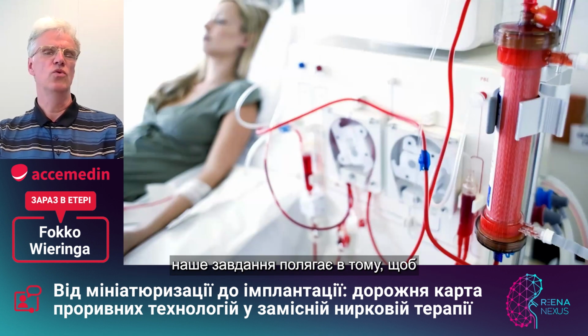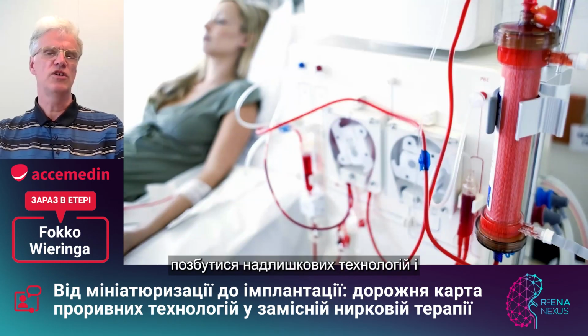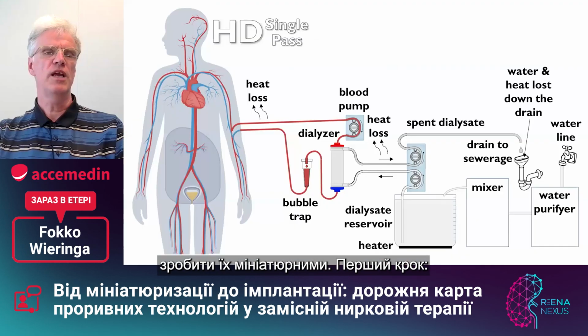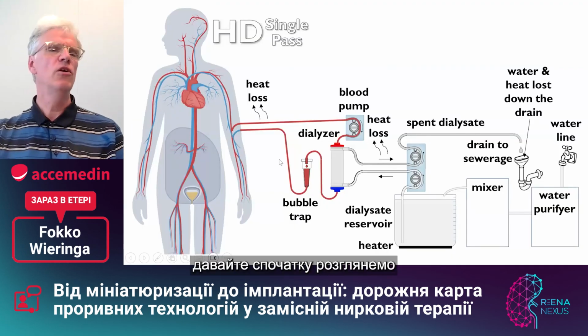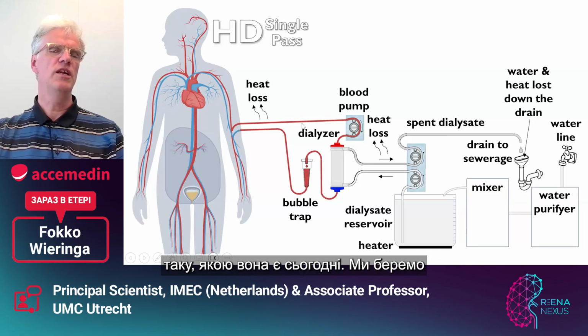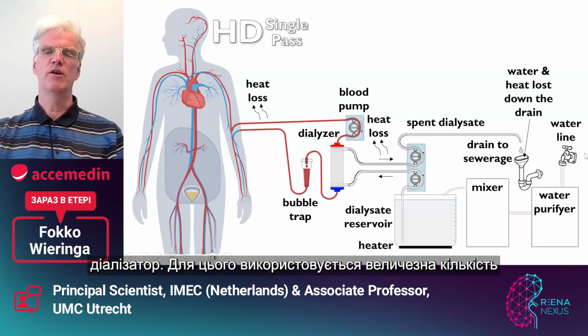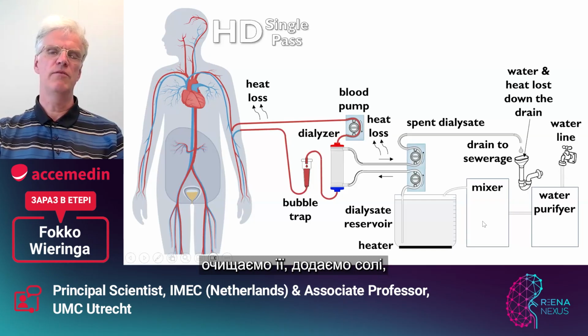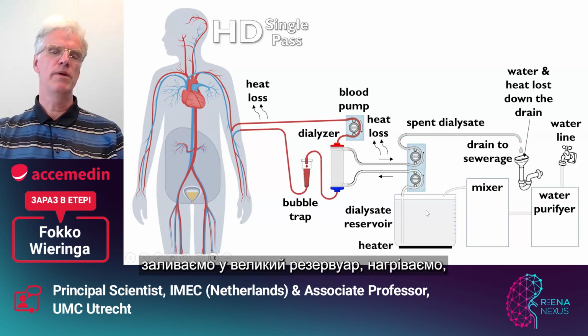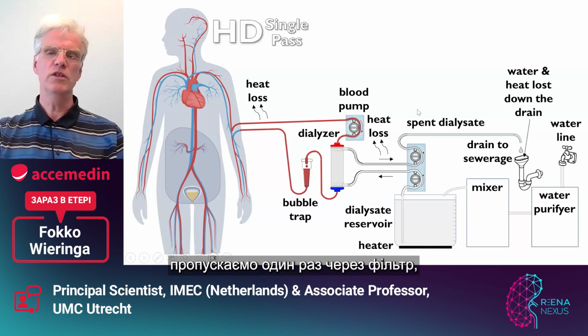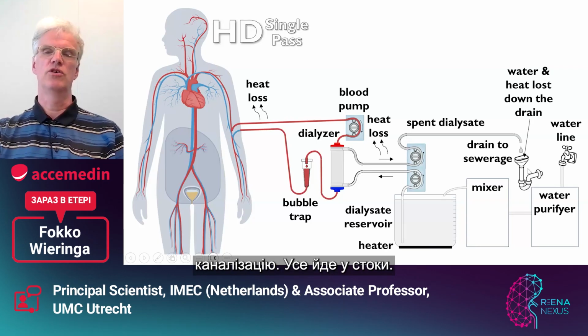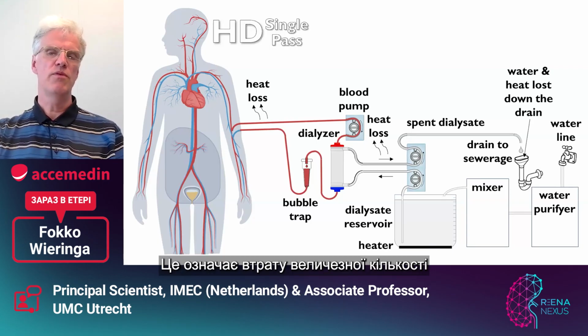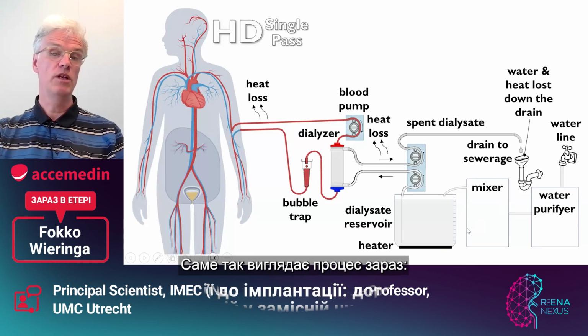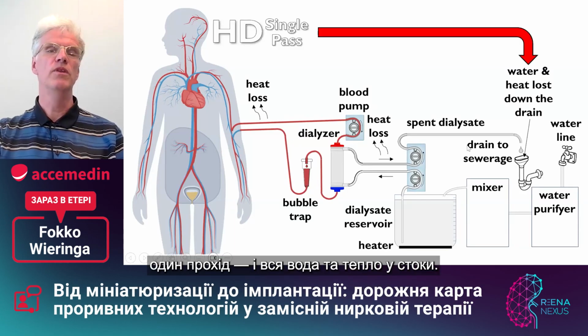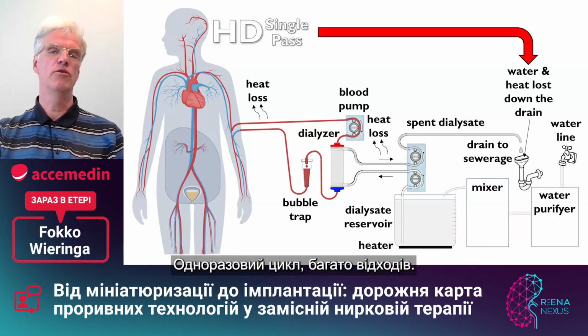So what we try to do is to get rid of these technologies and miniaturize them. The first step, let's first take a look at a typical single pass normal machine as they are now. We take the blood from the body, we pump it through a dialyzer. We also have a huge amount of water that we take from the line. We purify that, we mix the salts, we throw it in the big reservoir, we heat it up, we pump it through the filter once, and then we throw it away in the sewerage. We throw it away to the drain, which means we throw away a huge amount of water and a huge amount of electricity that we needed to heat up that water. That's how it is now. Single pass, loss of water and heat down the drain.